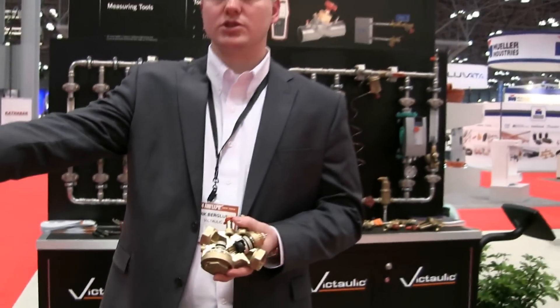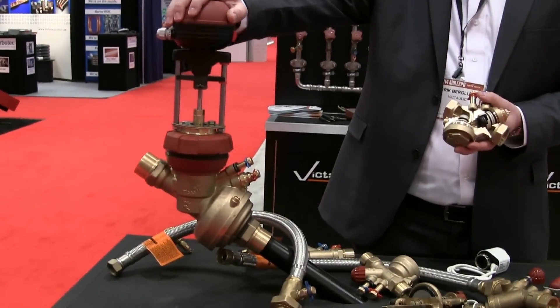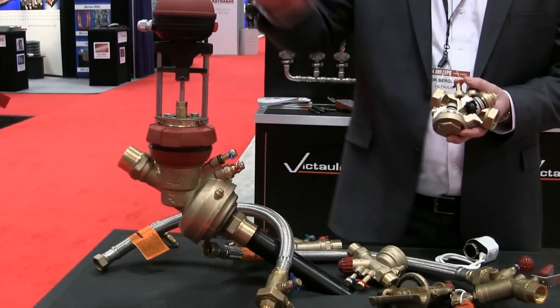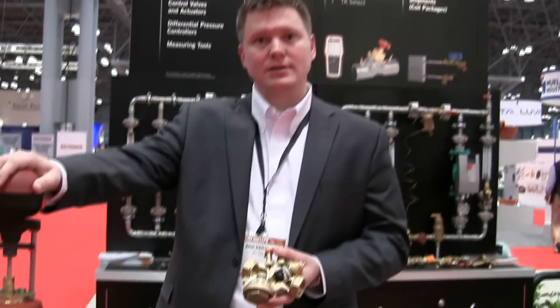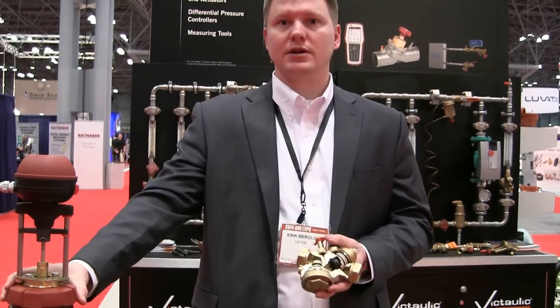Anything over one inch goes into our Fusion line. The TA Fusion is a new valve that goes up to six inches. It does the same thing as the TBC — Terminal Balancing and Control — removing the need for a balancing valve by having an adjustable CV built in.